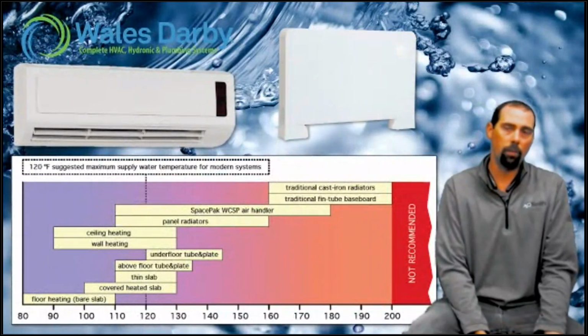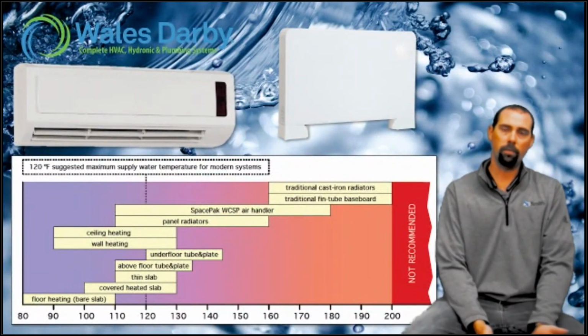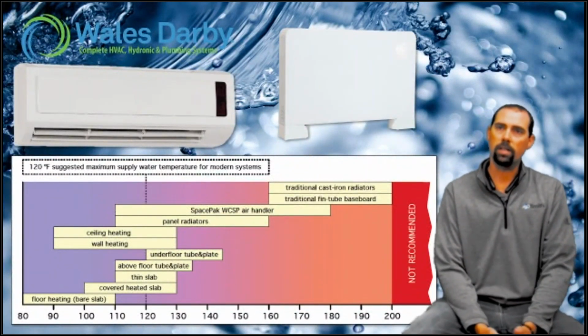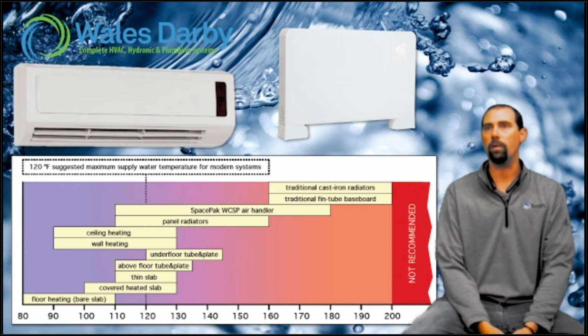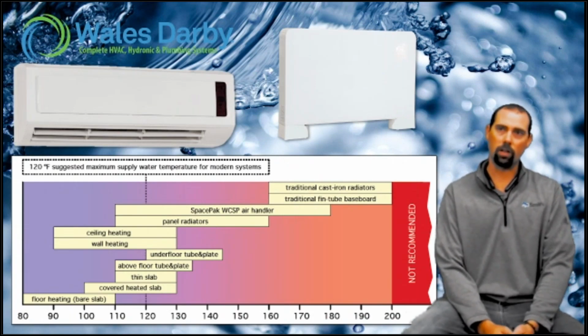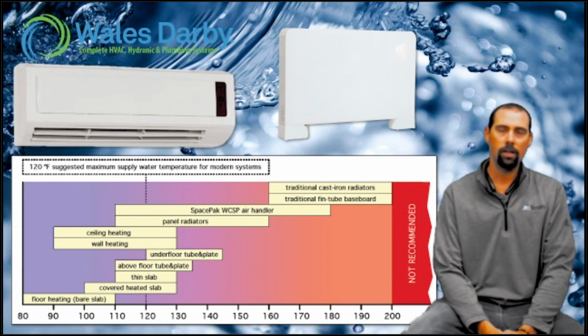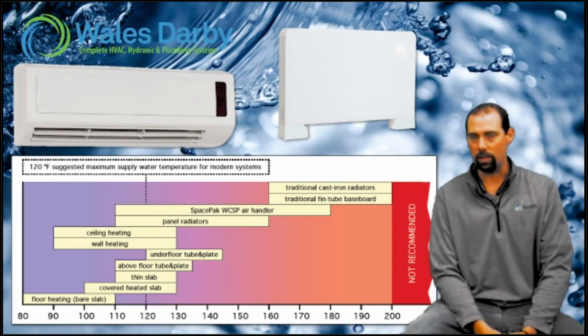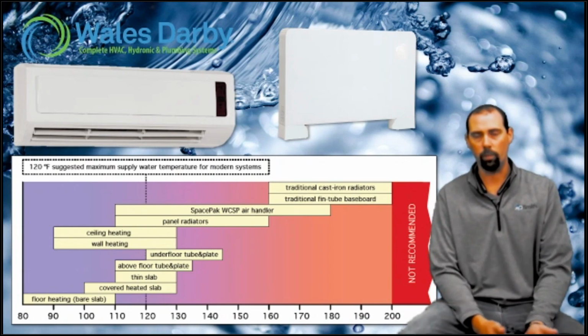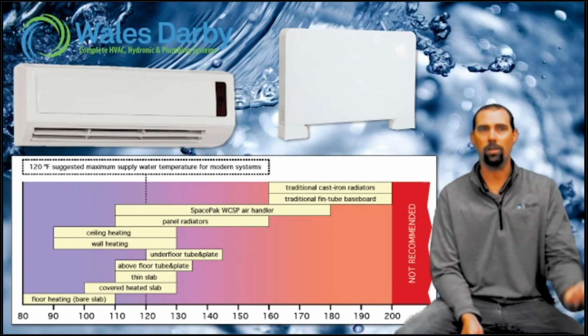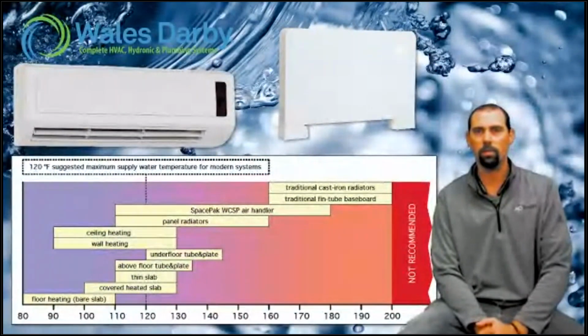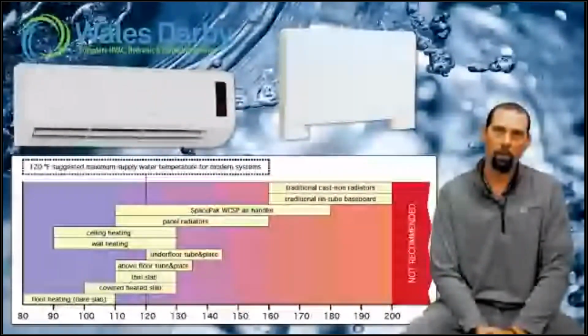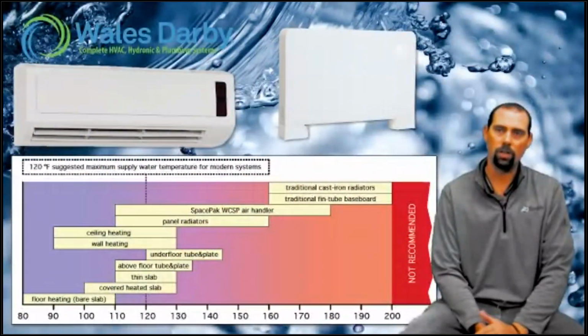Then we've got what we call our thin wall, which looks very similar to a panel rad, but it's got an ECM blower in there - very efficient, very quiet, with a nice glass front and a touch screen. We did some math with this - we were able to, at certain water temps, replace up to 19 to 21 feet of baseboard. It's considerable, and that was just the mid-size unit.